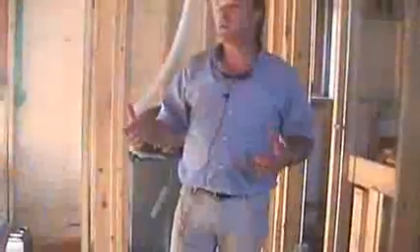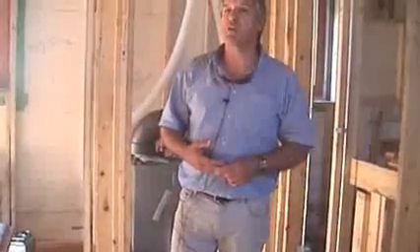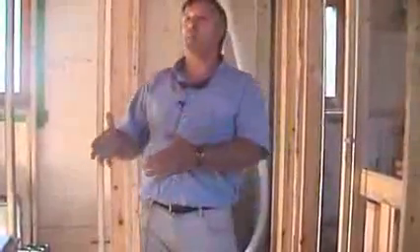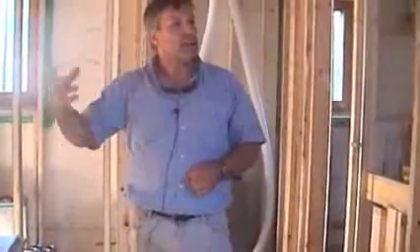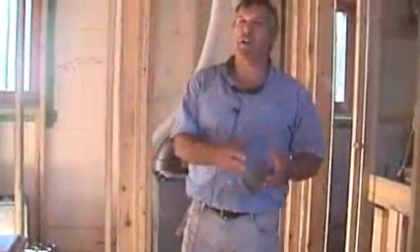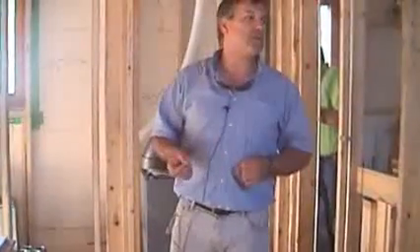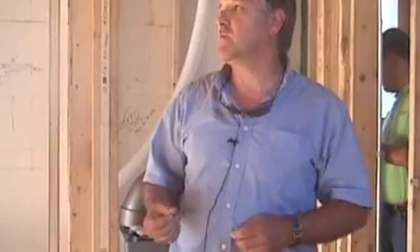So we plugged in several parameters. One of those is the air changes overall for the house. We took the volume of this house, and the passive house standard is 0.3 air changes per hour. So we took the complete total volume and figured out what the minimum supply air and turnover in the house should be. Then we plug in all the exhausts. The passive house standard for continuous ventilation is 24 CFM per full bath, 12 CFM for a half bath, and 35 CFM out of the kitchen area.